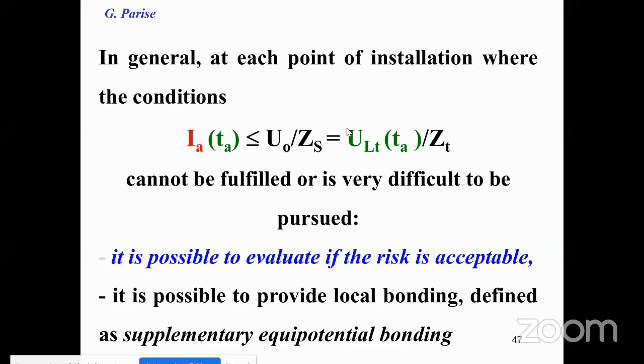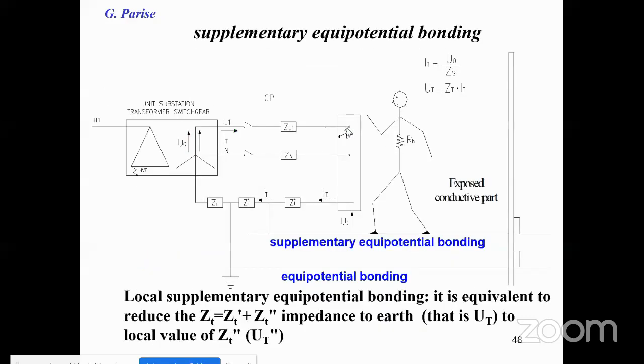How important is local supplementary equipotential bonding, especially in a TN system? You can understand that the exposed conductive part is connected to the main grounding electrode, but locally, in a local panel, all the components connected to ground, like exposed conductive parts and extraneous conductive parts, are connected also locally. The impedance of the protective conductor is subdivided in fractions, and so the local touch voltage is reduced, and the safe conditions are enhanced.